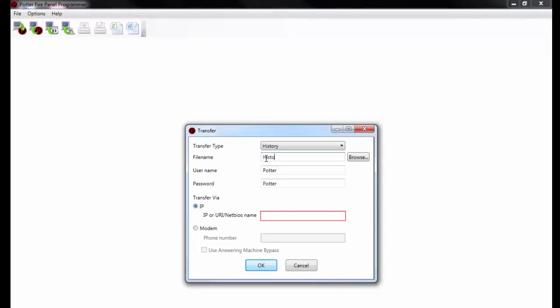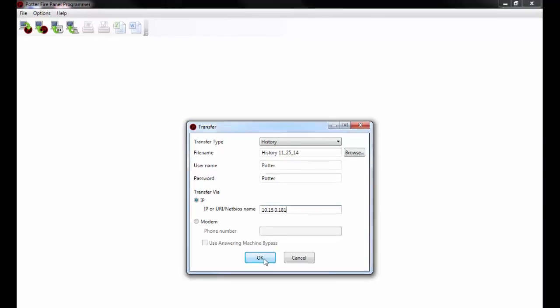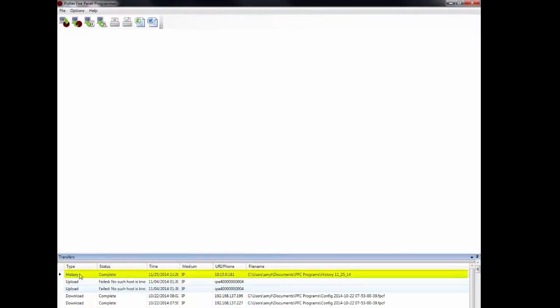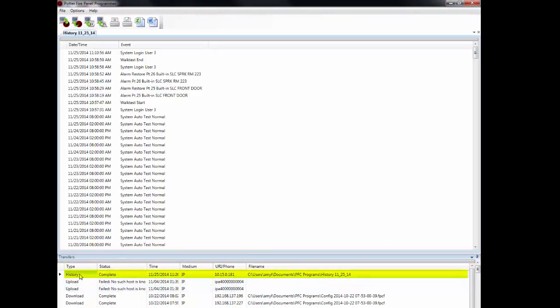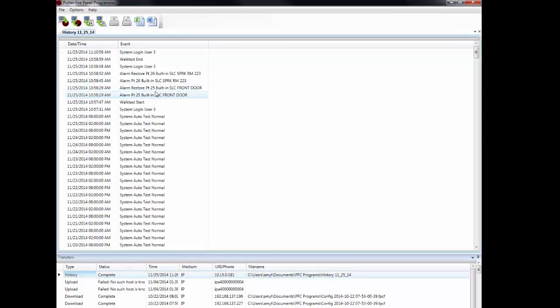Give this a file name. Put in your username and password and then type in either the IP address of the fire alarm control panel or the panel's name, and then go ahead and click OK. This will upload the history that is inside the fire alarm control panel, and now you can print this or save this to an electronic file and you have the site history since the last visit.